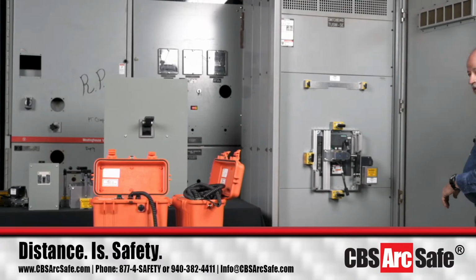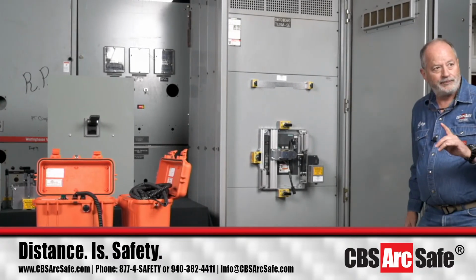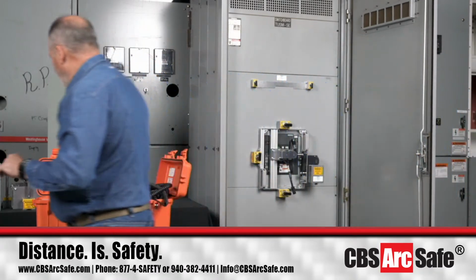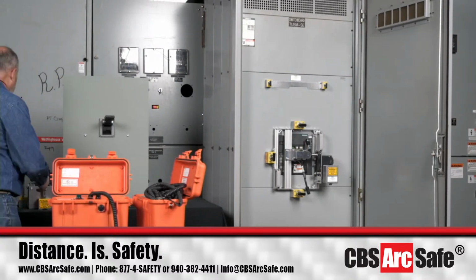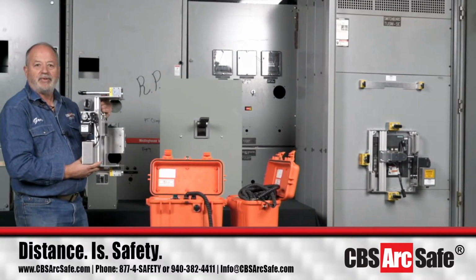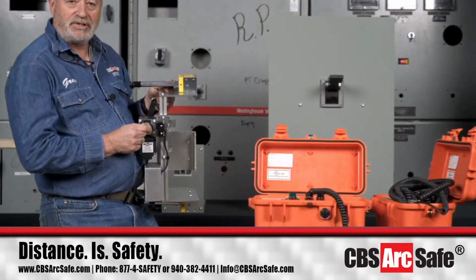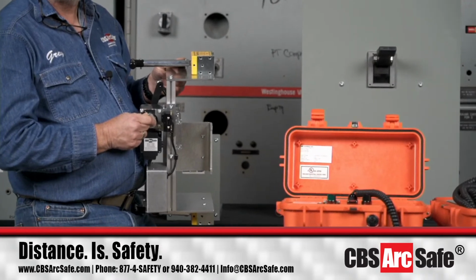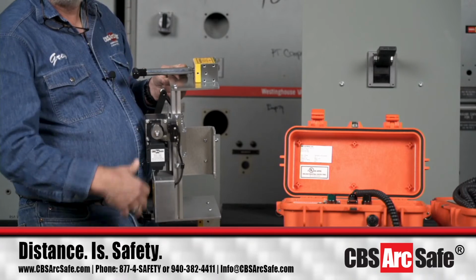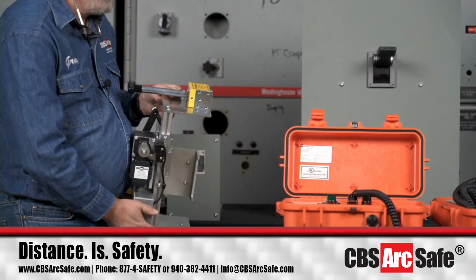Now, Greg, can you explain on the RSA you just showed how the RSA knows when to stop its travel? Kyle just brought up a good question: how does this remote switch actuator know how to stop in the right position for close and open? We have a couple of cam switches here on the side so that we're not going to over travel the distance. That way we'll make sure that we're going only to the limits of the handle itself for the operation of the remote switch actuator.